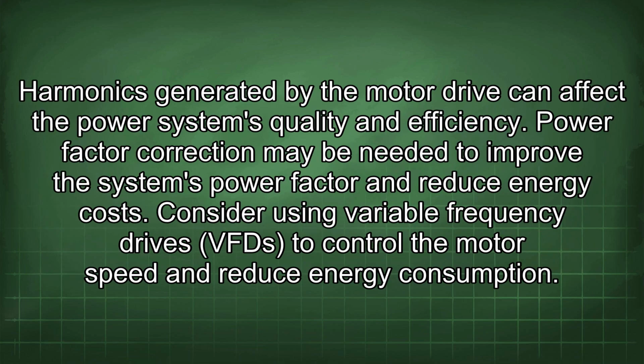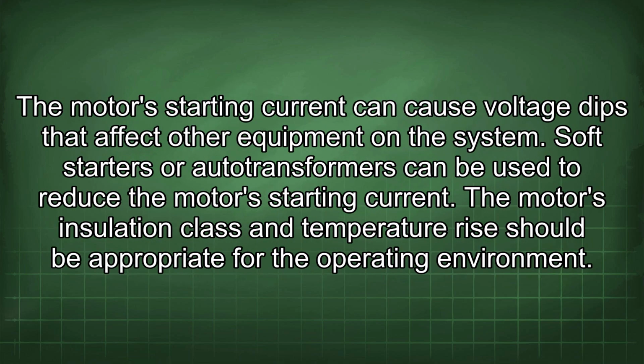Harmonics generated by the motor drive can affect the power system's quality and efficiency. Power factor correction may be needed to improve the system's power factor and reduce energy costs. Consider using variable frequency drives (VFD) to control the motor speed and reduce energy consumption. The motor starting current can cause voltage dips that affect other equipment in the system.